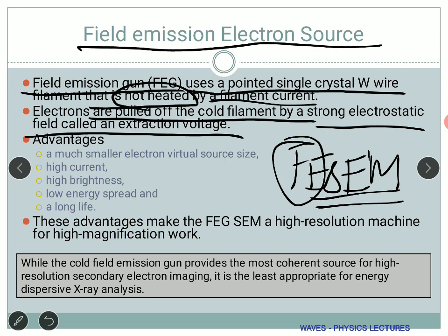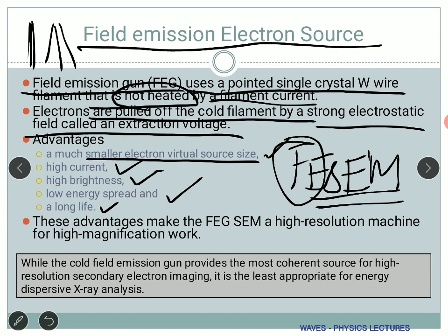The advantages of FEG are: long life, because the filament is not being heated so mechanical stress is much less; a much smaller electron virtual source size since the diameter is very small; high current and very high brightness; and less energy spread — the beam is narrow and focused rather than spread out. These advantages make the field emission scanning electron microscope a high-resolution machine for high magnification work. In current research, good journals typically expect FESEM images rather than regular SEM.